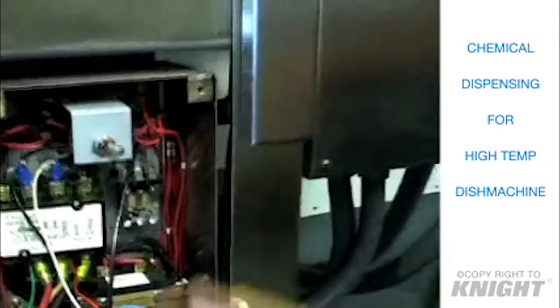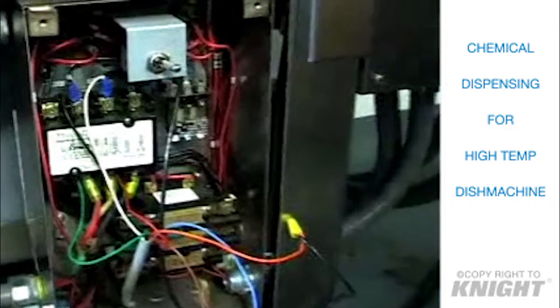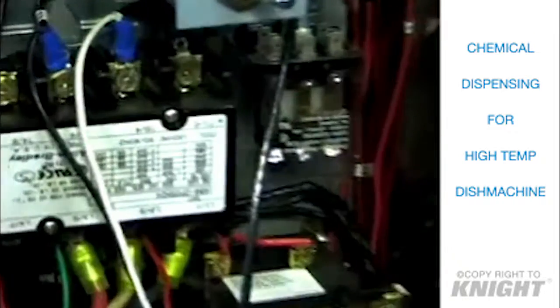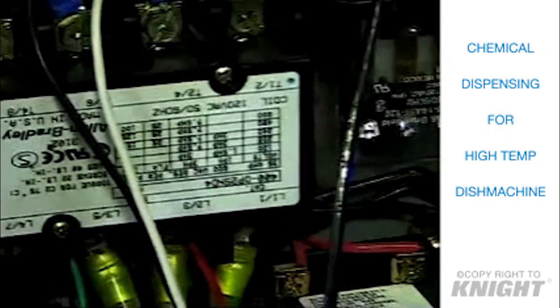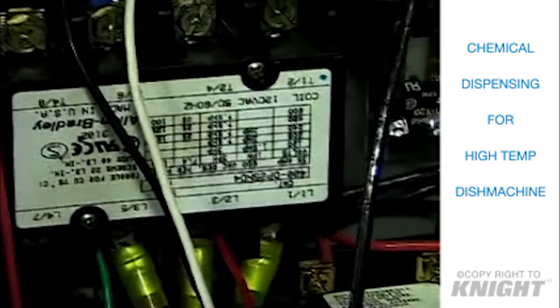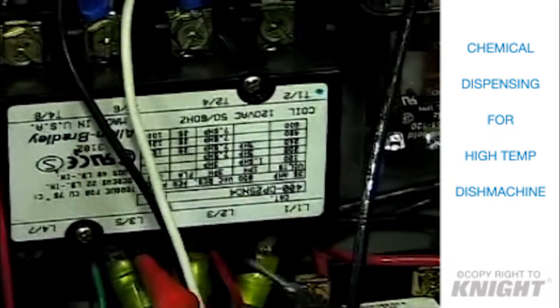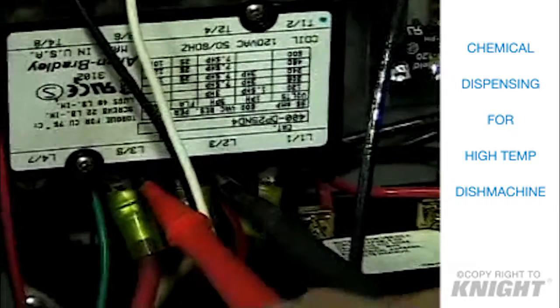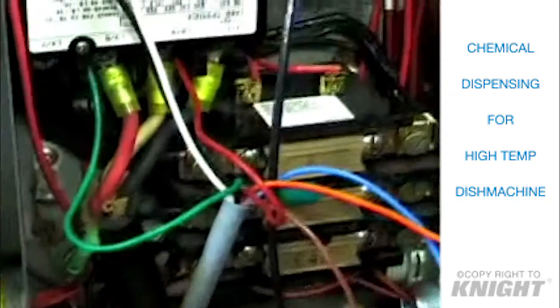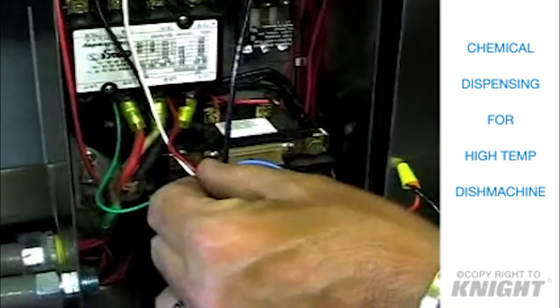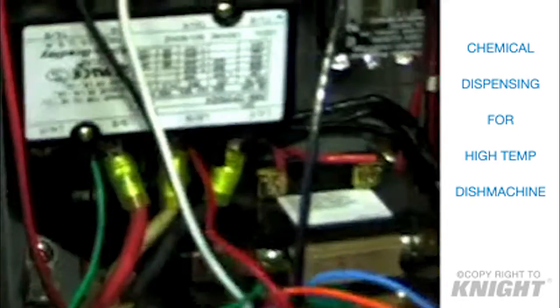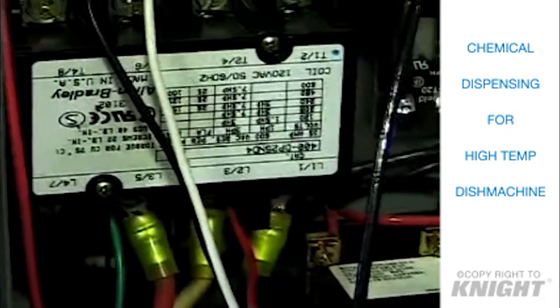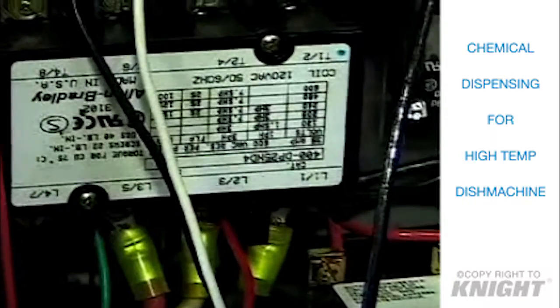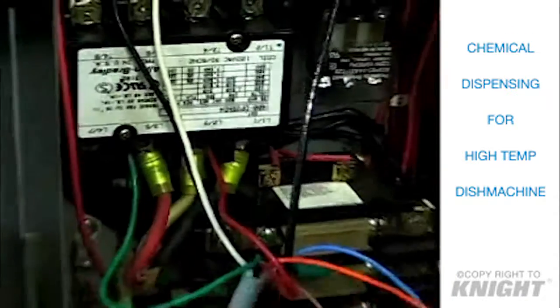Next, you'll see that this is a magnetic contactor. The magnetic contactor has a line side down here, and if I do a test for you right now, I'll just show you on my voltmeter that I have power. This machine's 208 volts, and as you can see, I have 215 volts. Okay, and I have a green wire and a red wire hooked up to this, so there's power to my DigiSet, and that's why when we looked at the DigiSet earlier, you could see that the power was on. Now it's not going to operate, but it's ready to operate.